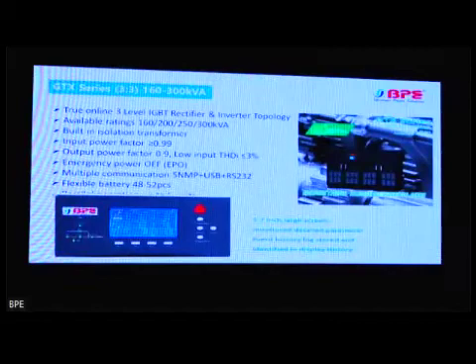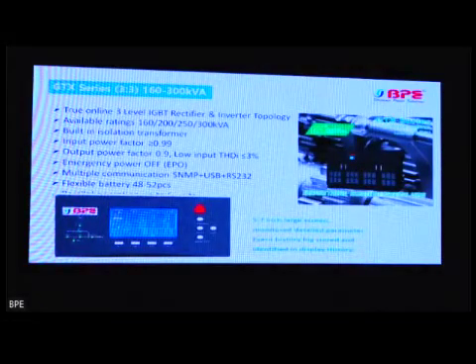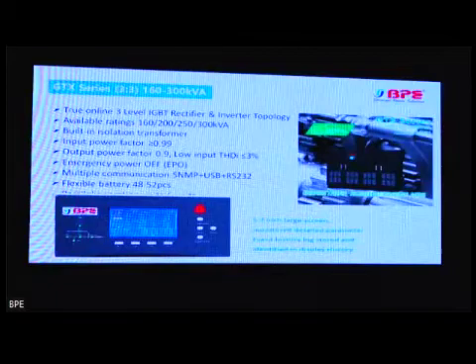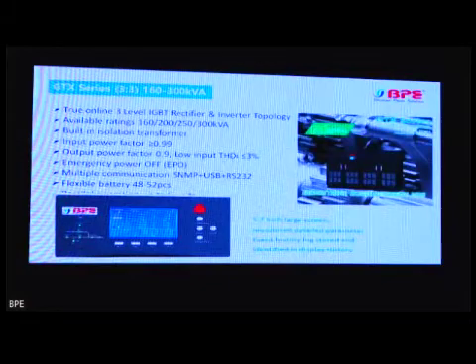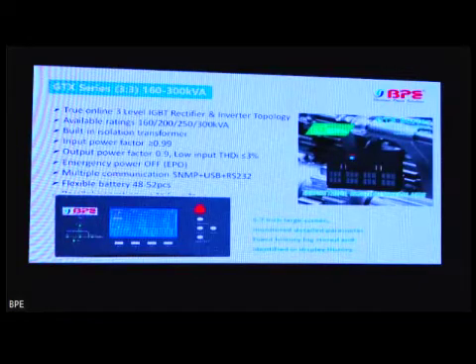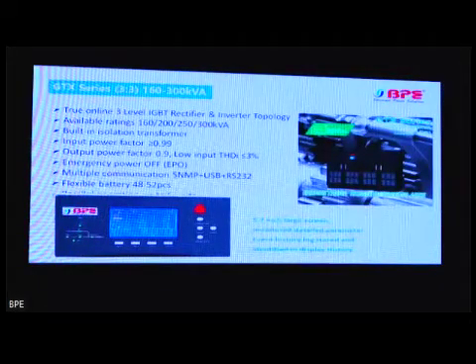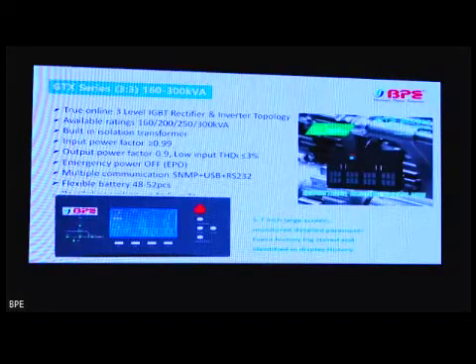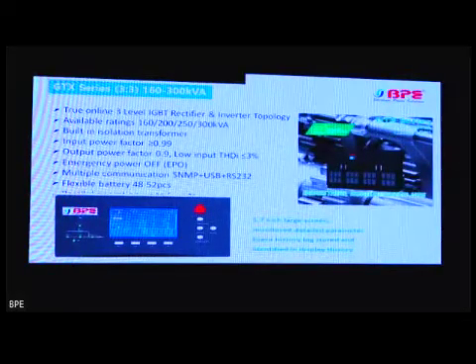Then we have GTX series, which is up to 300 kVA. And this has got very high input power factor greater than 0.99. Available ratings are 160 kVA, 200, 250 and 300 kVA. And the output power factor is 0.9. Flexible batteries are there from 48 to 52. 5.7 inch large screen display is there with all the information for the customer. Emergency power off switch is there. This is also suitable applications.